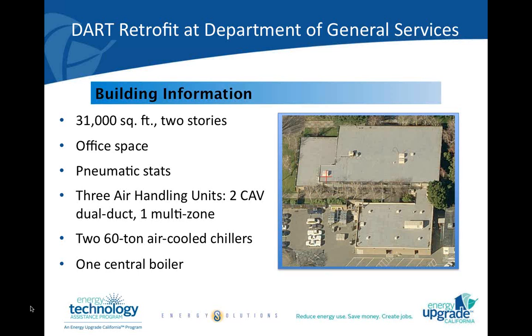These are all constant volume, dual duct units, and the one on the bottom is a multi-zone. So they have a hot deck and a cold deck, and these are pneumatic systems for the control at the zone level. We also have 2 air-cooled chillers that provide the chilled water, as well as 1 central boiler. And this is all basically office space.